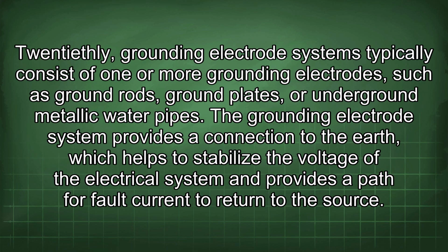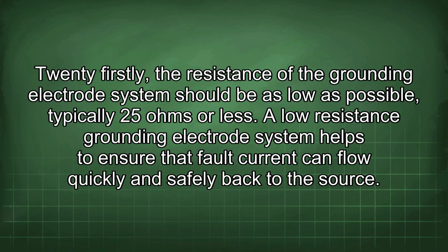20thly, grounding electrode systems typically consist of one or more grounding electrodes, such as ground rods, ground plates, or underground metallic water pipes. The grounding electrode system provides a connection to the earth, which helps to stabilize the voltage of the electrical system and provides a path for fault current to return to the source. 21stly, the resistance of the grounding electrode system should be as low as possible, typically 25 ohms or less.